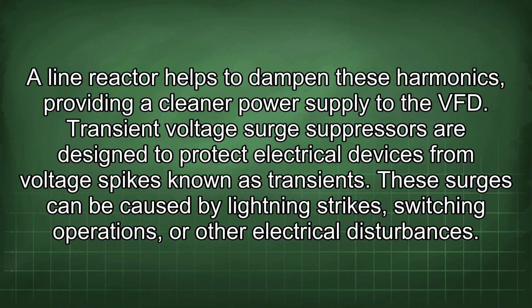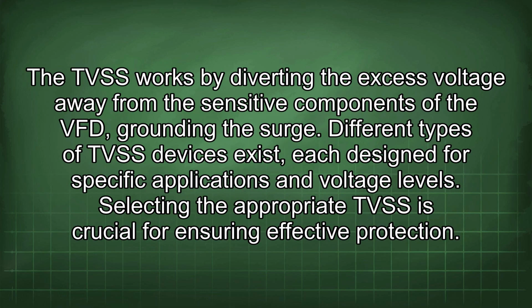Transient voltage surge suppressors are designed to protect electrical devices from voltage spikes known as transients. These surges can be caused by lightning strikes, switching operations, or other electrical disturbances. The TVSS works by diverting the excess voltage away from the sensitive components of the VFD, grounding the surge. Different types of TVSS devices exist, each designed for specific applications and voltage levels. Selecting the appropriate TVSS is crucial for ensuring effective protection.